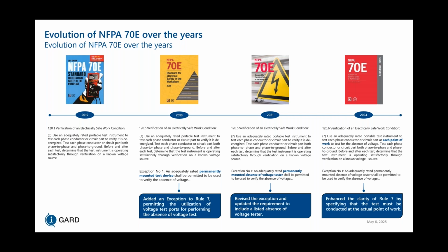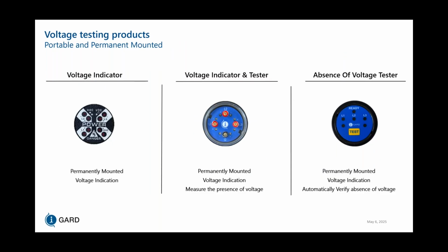So what's the difference between a voltage test port and an absence of voltage tester? Well, that's what this presentation is for, and we will go through all the details. To start off with, a voltage indicator basically has LED lights for each of the 3 phases as well as for ground, and indicates that there's voltage present when the LEDs are lit up, essentially. Then we also have voltage indicators and testers, which combine the LEDs alongside voltage test ports, which can be utilized to measure line to line and line to ground voltage on the front of the door. Then an absence of voltage tester is a permanently mounted unit that contains LEDs and a test button, which automatically tests the line to line and line to ground voltages to confirm absence of voltage with just the test button.